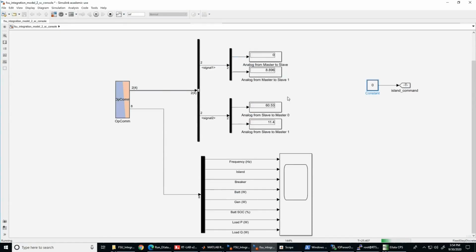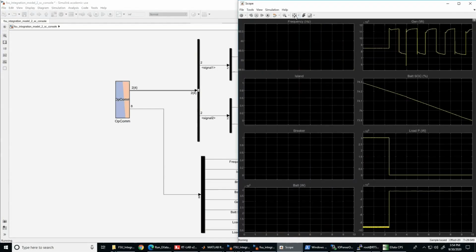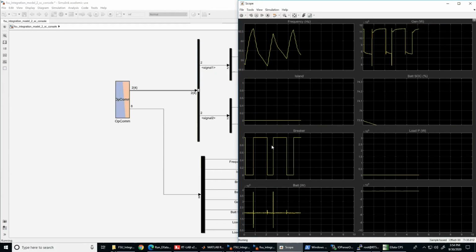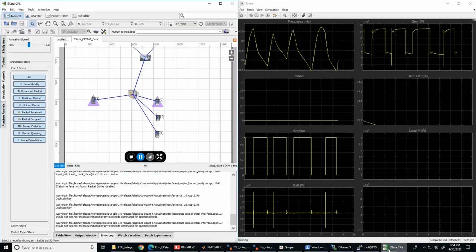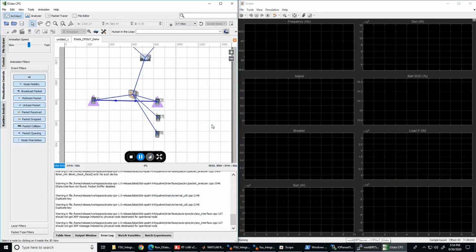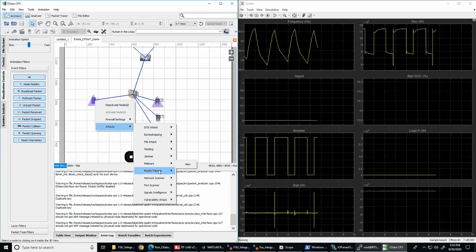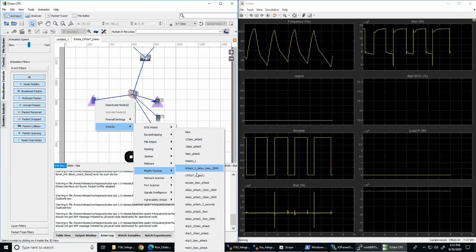It is important to mention that in order to show the impact of the time delay attack in our running real-time system, we designed the experiment in a way that the master controller will shed the load only when the frequency goes below a certain threshold, in our case 59.3 Hz, and will reconnect it when the frequency goes back to the nominal 60 Hz. We understand that this may not be the way microgrid protection works in a real scenario, but for demonstration purposes, we designed the experiment this way, so we can clearly show how a time delay attack can affect the system and not permit the controller to shed the load due to the delay of the measurements received. That is why you see the frequency of the system fluctuating, and this is because of the shareable load being connected and disconnected at the respective thresholds.